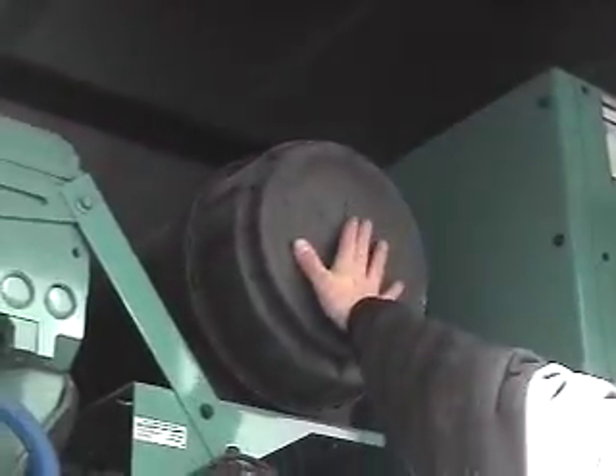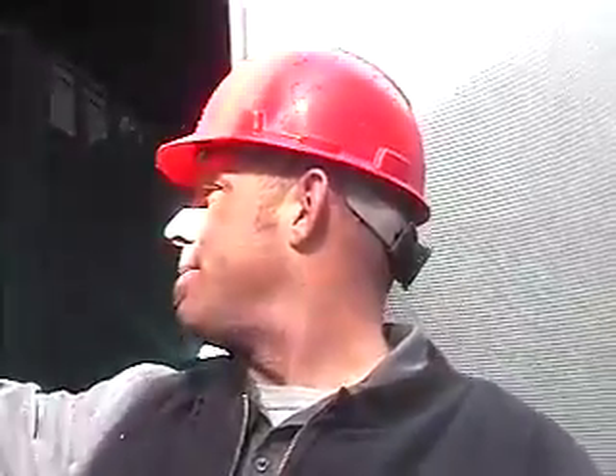The air filter is in this door here, and there's a vacuum gauge on the other side I'll show you. The new fuel, oil, or air filters are pretty simple to change. In standby cycle operation, I've changed them more because they're old and falling apart, more so than because they're full of dirt. So let's continue walking around.